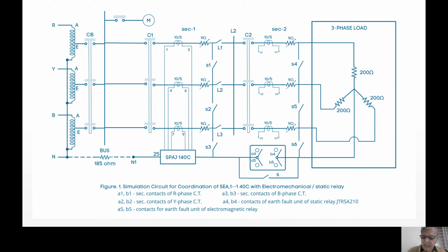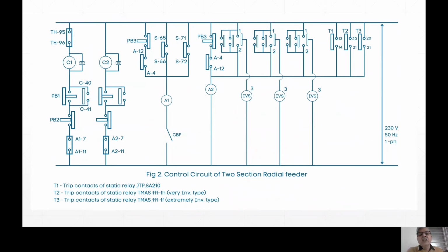So this is the AC circuit, power circuit. Control circuit, you have to wire. Control circuit means when the relay operates, the contactor should automatically trip. C1 is the contactor for first section. C2 is for second section. C2 is controlled by electromagnetic and static relay. So you can see that on right hand side, 3 relays are there, right? These are electromagnetic relays. So when they operate, operation of IVS will operate A2, that is the auxiliary relay. And when A2 operates, A2 7 and A2 11 will open out and breaker C2 will de-energize. Rather, that will isolate the faulty section, right? Using A1.